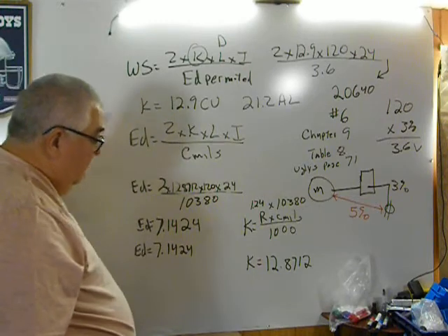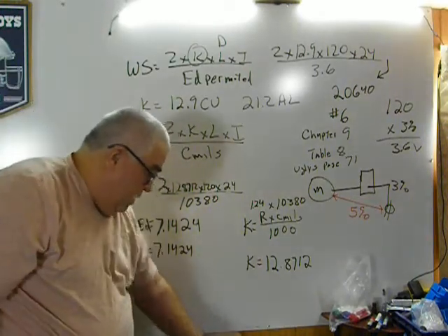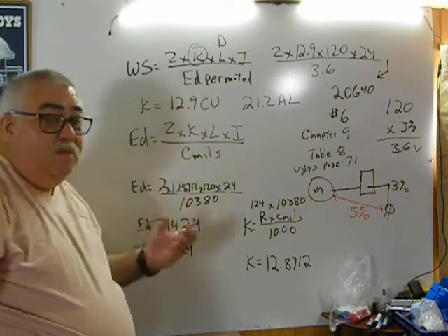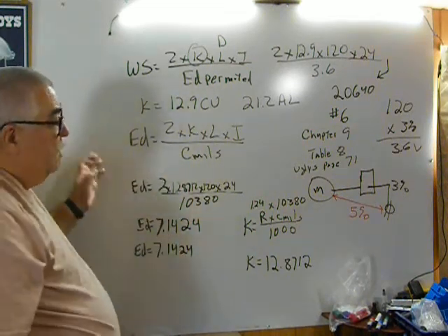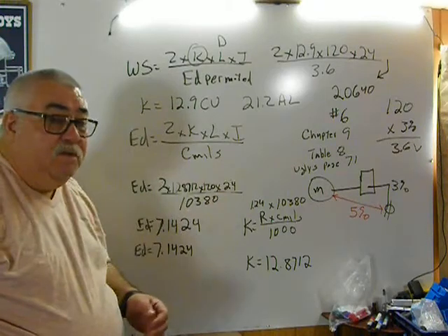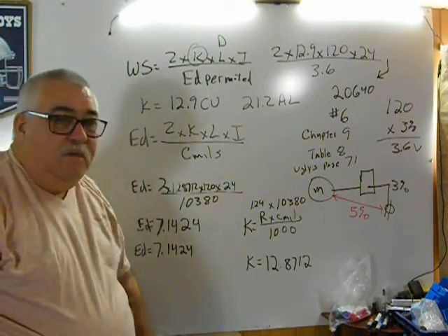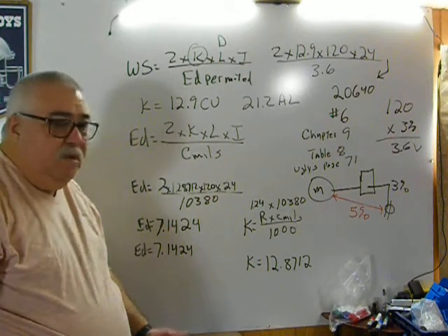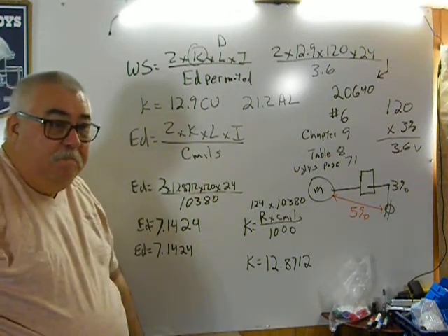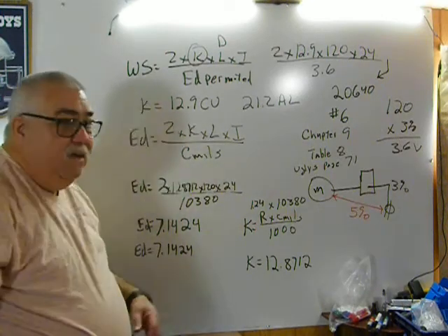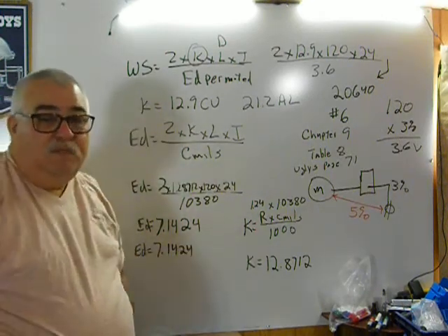Voltage drop, again, is not a requirement in the code. It's not something that you have to do. Voltage drop is something you should look at because of efficiencies. Again, which one you use, how you do it, is up to you. I can only give you the formulas, and then you use what's easiest for you.